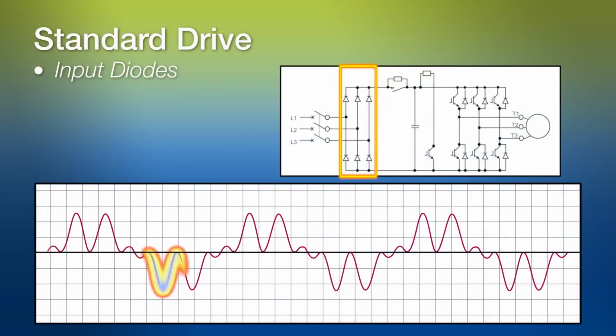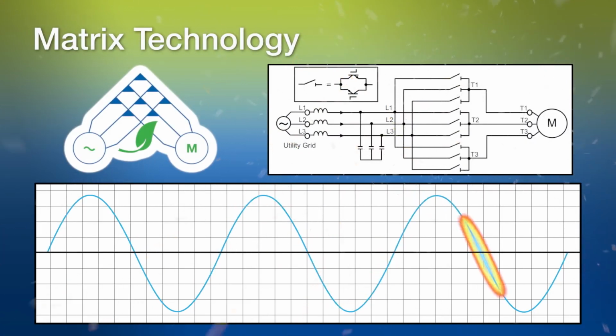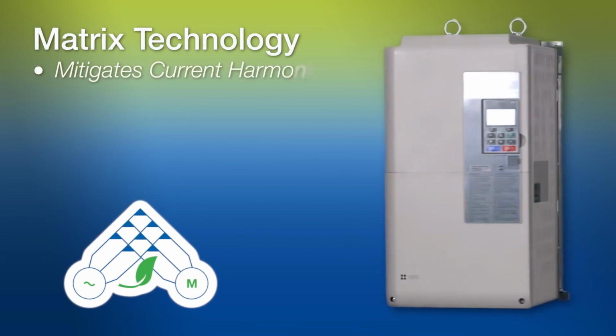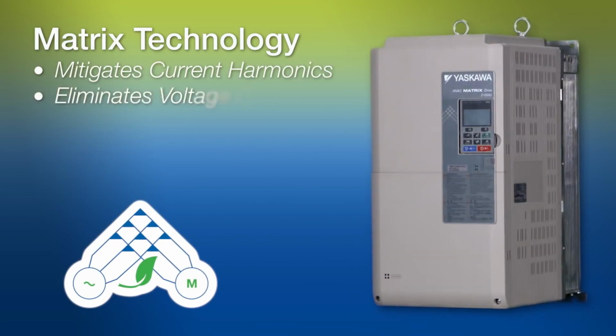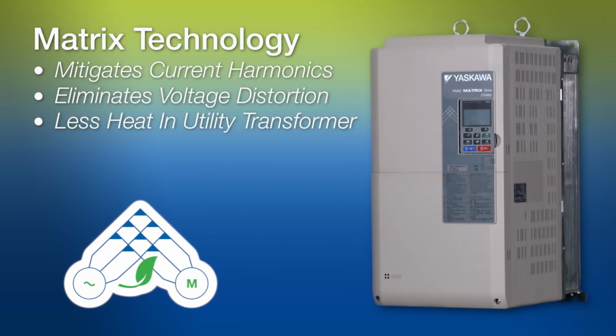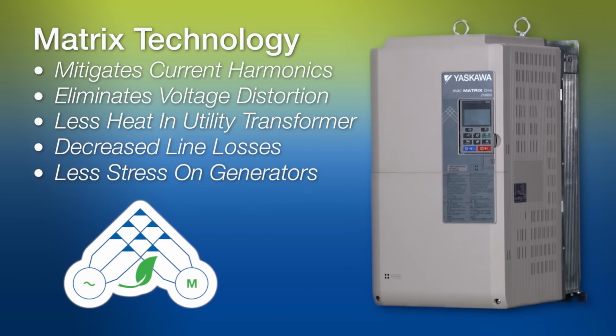The input diodes on a VFD result in nonlinear current consumption on the connected power supply. By eliminating this input diode bridge, the input current waveform becomes sinusoidal with the connected power supply. This mitigates current harmonics and, in turn, eliminates voltage distortion sent back to the power grid. The result is less heat in the utility transformer, decreased line losses, and less stress on generators, all due to the matrix drive's state-of-the-art design.